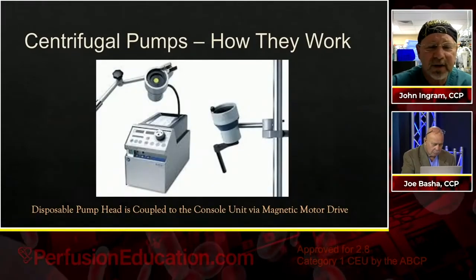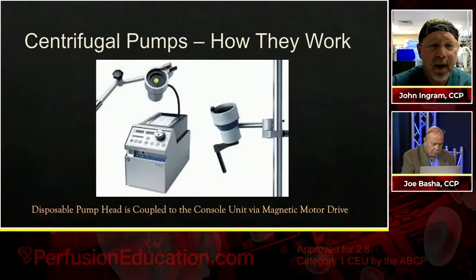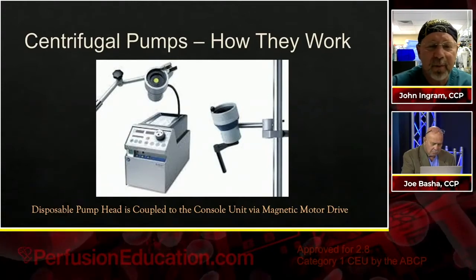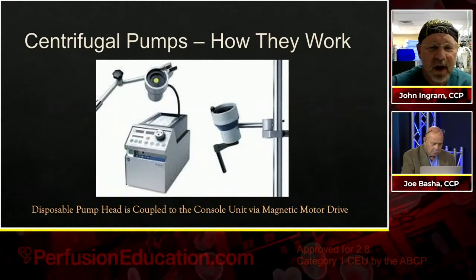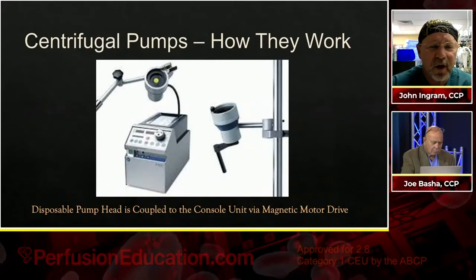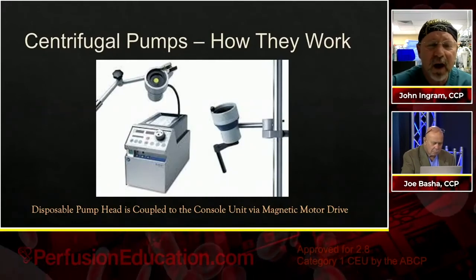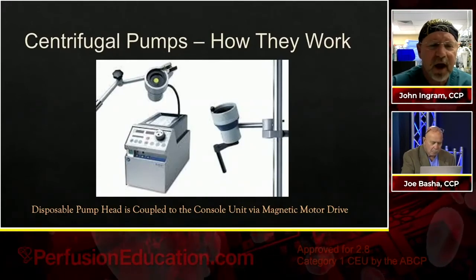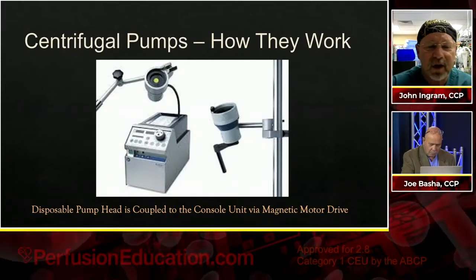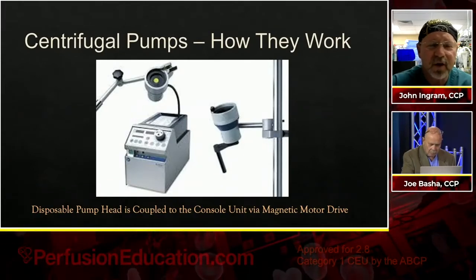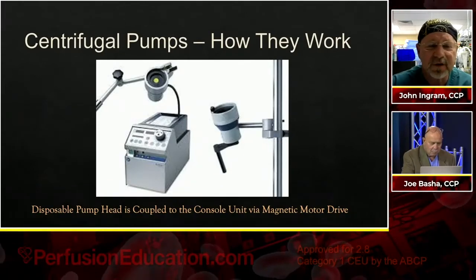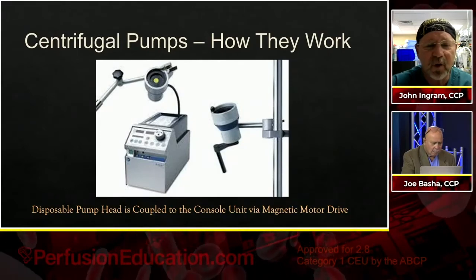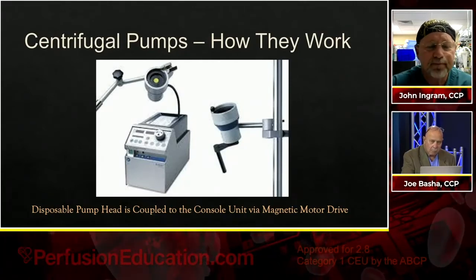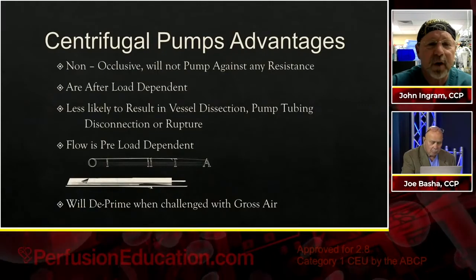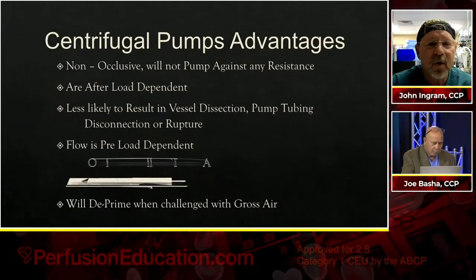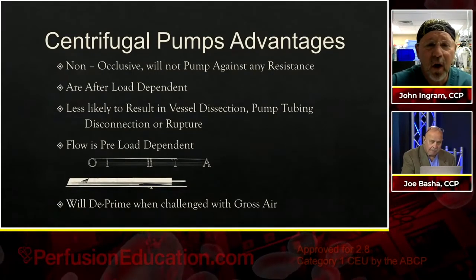So as I said about the magnetic coupling, these disposable pump heads you just saw need to go into some type of console unit. The disposable has a magnet on the base of it, and that couples magnetically with the console unit. The console unit then spins and causes also the disposable unit to spin at the same speed. But you can have decoupling as well, right? Yes. We're going to talk about that. So some of the disadvantages.